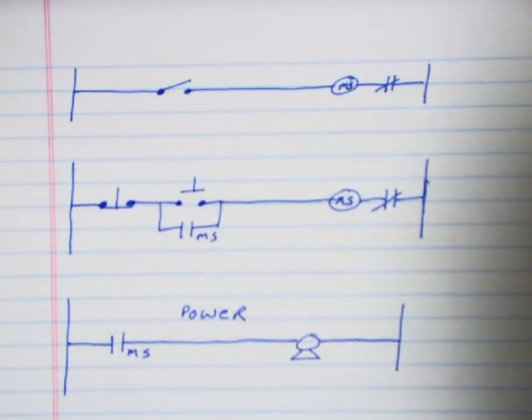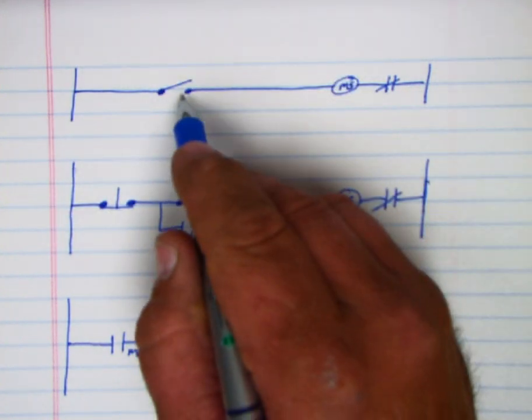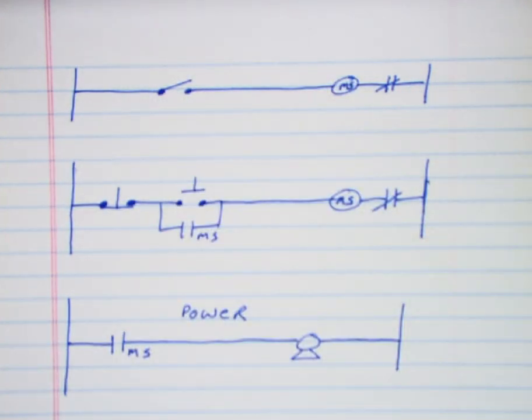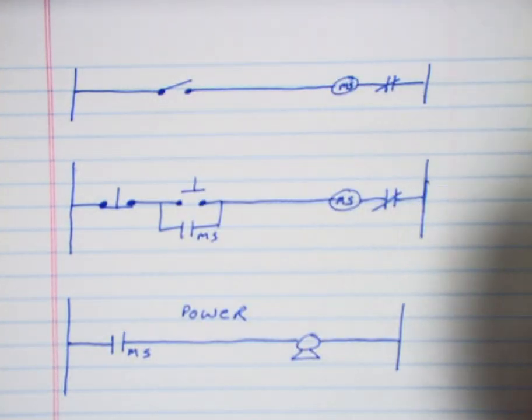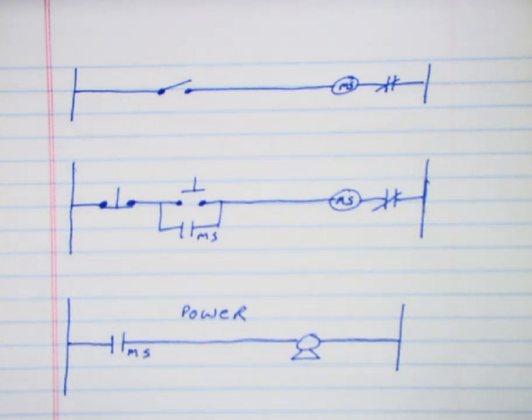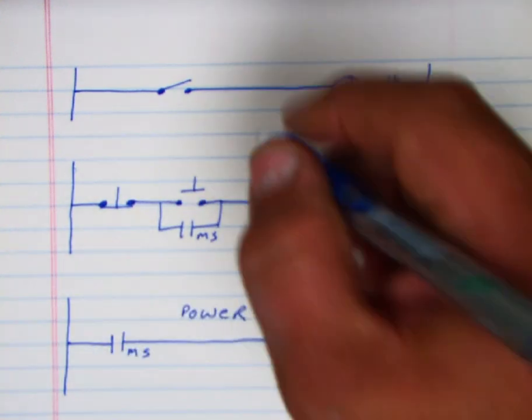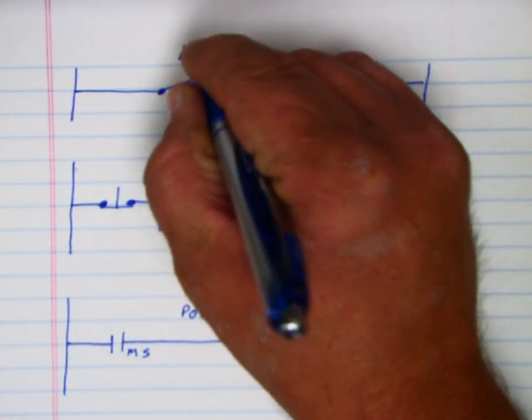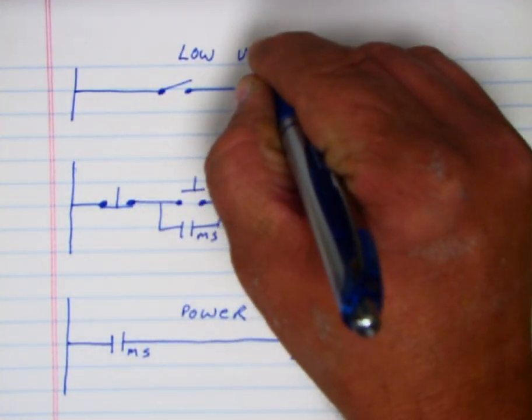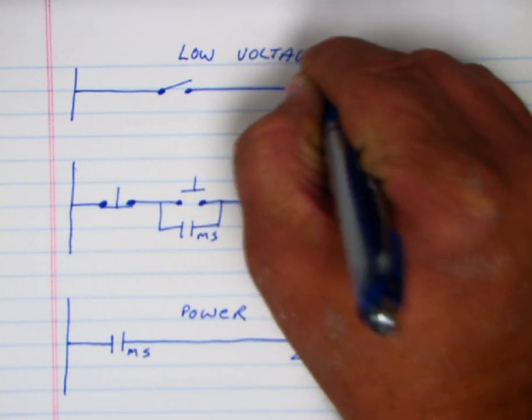Now, this top version here uses a maintained switch to turn this motor starter, to energize the motor starter coil, which pulls in our contacts and turns this motor off and on. If we're using a maintained switch up here, so just a toggle switch, could be a light switch on a wall, we call this low voltage release.